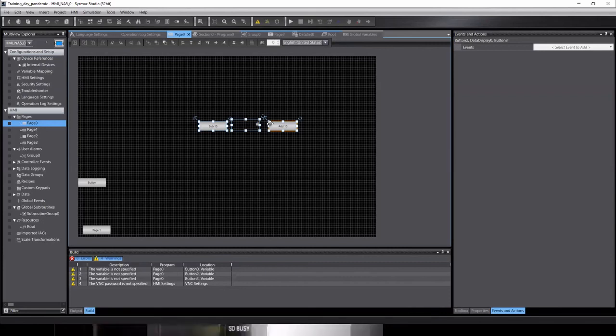So I made a script and I made a few variables on the HMI to essentially have a watchdog timer go to a certain page when it would lose communication with the PLC. I could have that internal variable trigger an alarm, just like I could have a PLC variable trigger an alarm. So we'll do this exact same +10, -10 setup, but we're going to instead use an HMI variable instead of a PLC variable.